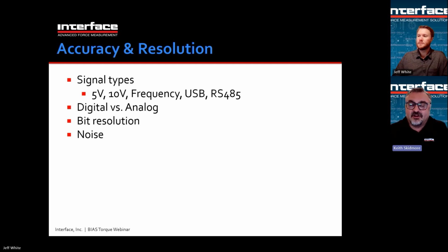Now, sometimes customers cannot deal with a negative voltage, so we can offset the voltage. We could have 5 volts at 0 torque, then 0 volts at full counterclockwise and 10 volts at full clockwise. That's possible, but that's a special, and typically they're not set up that way unless specified. For frequency, instead of a voltage, you might have a frequency output: 10 kilohertz at 0 torque, going up to 15 kilohertz full clockwise, and all the way down to 5 kilohertz full counterclockwise. Of course, USB or RS-485 would be delivering processed data, so Newton meters as a digital packet. Digital versus analog: an analog sensor can't have something like RS-485 or USB. A digital sensor may be digital internally, but then converts back to analog for the signal.